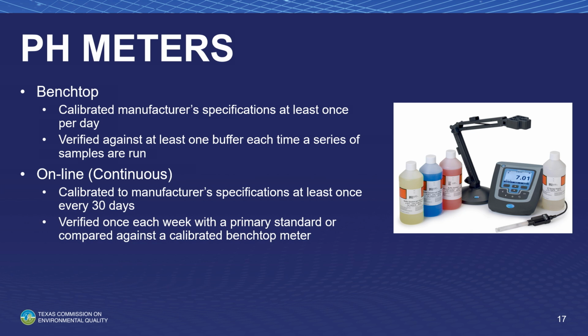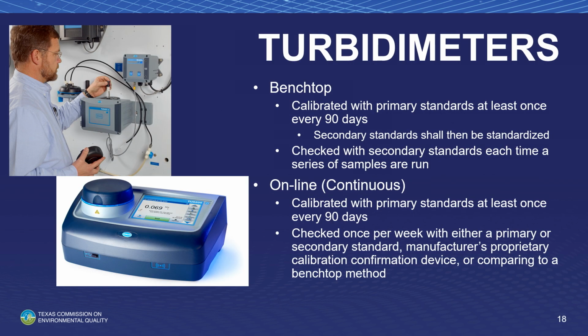Online continuous pH meters need to be calibrated to the manufacturer specs at least once every 30 days, and then verified once each week with a primary standard or compared against a calibrated benchtop. Turbidimeters, the benchtops need to be calibrated with primary standards at least once every 90 days, so essentially once a quarter. Secondary standards shall then be restandardized. Check the secondary standards each time a series of samples are run.